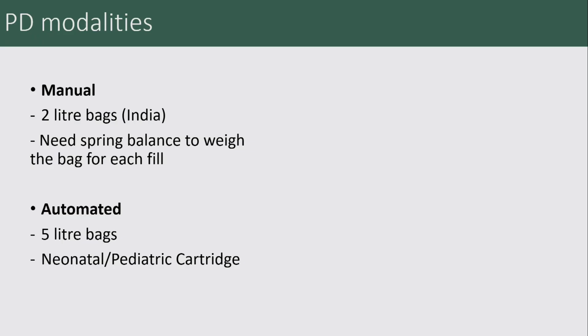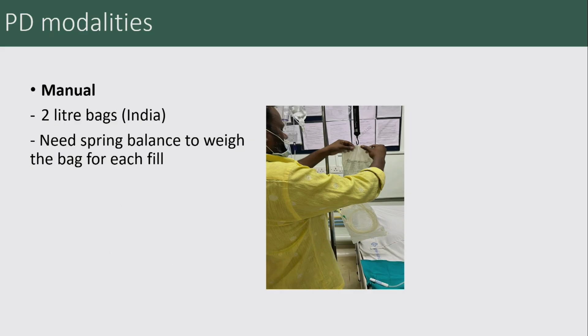So that is the manual bag, because we have only 2 liter bags. Then we have automated bags, where a 5 liter bag can be used, and we have a neonatal or child cartridge, so the machine will guide how much fluid is going in. This is definitely comfortable and can be used particularly for nighttime dialysis. Again, a 5 liter bag for daytime will last for the entire day, so we can stick the child to the machine for the entire day. It is mainly used for nighttime dialysis.